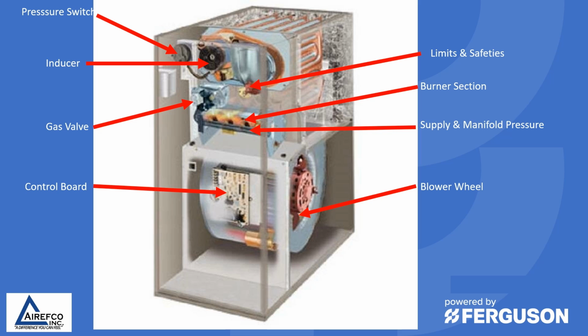When the filters are not changed periodically, as they should be, the blower wheel can build up dust and corrosion. This will limit the efficiency of the blower wheel to move and circulate the air through the furnace. So make sure you double check the blower wheel to make sure that it's not caked up with dust and debris and that it's moving the air as it's designed to.